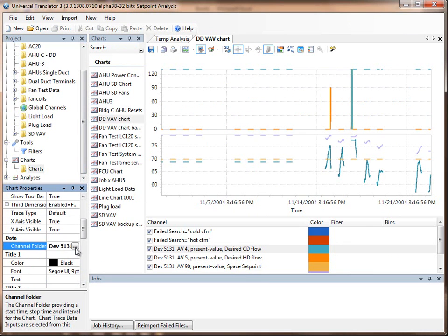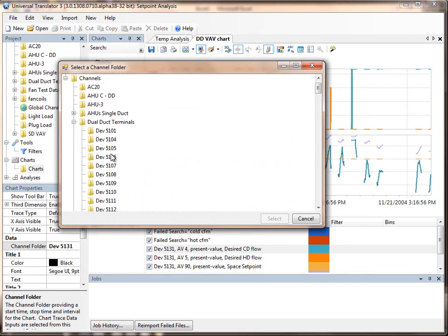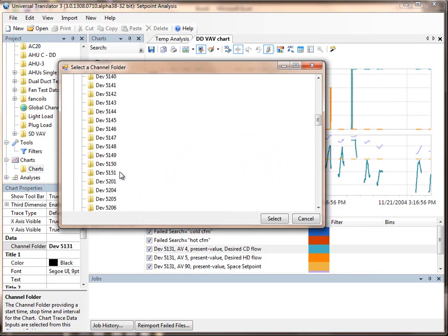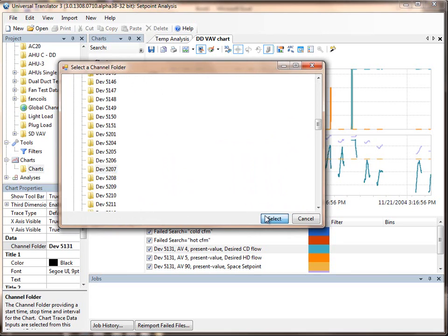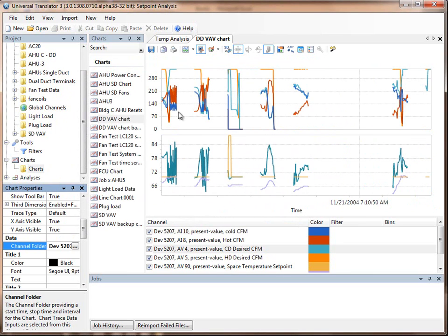So looking at 5207, let's take another look at the template graph. So this should be our coldest zone. And we can clearly see in the purple chart there at the bottom, low values, and at the top, heating and cooling dampers appear to be hunting. So maybe the zone is unstable, but certainly the results are too cold, no question about that. So there are values like 66, 67 degrees down here. So obviously that is going to cause comfort complaints.